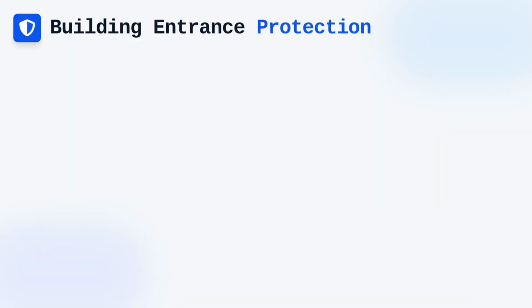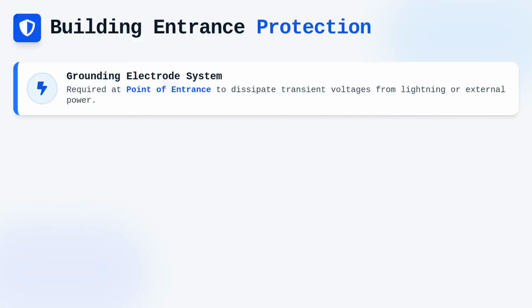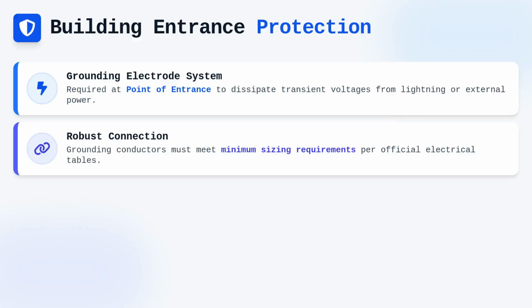Beyond cabling, the code mandates strict requirements for the protection of the building entrance. We must implement a comprehensive grounding electrode system at the point of entrance to dissipate transient voltages from lightning or external power contact. The connection to the grounding electrode system must be robust, usually via a grounding conductor that meets the minimum sizing requirements outlined in the electrical tables.